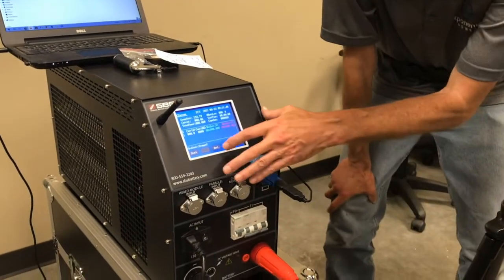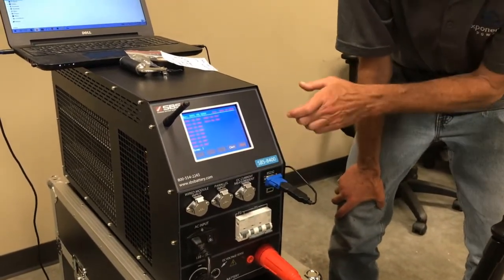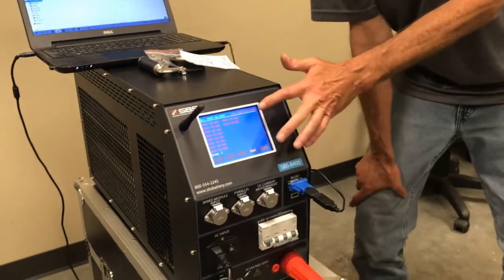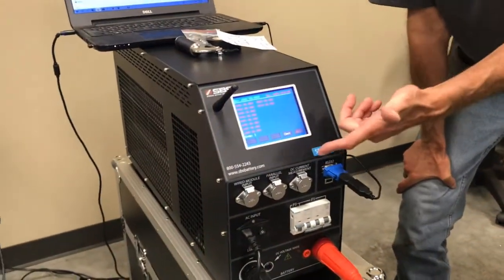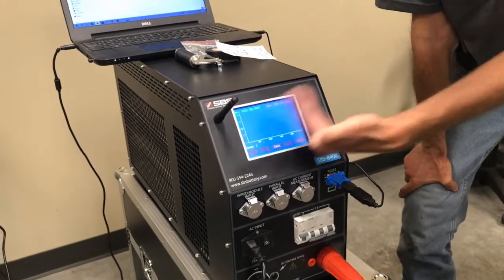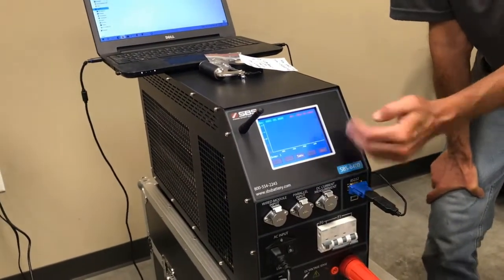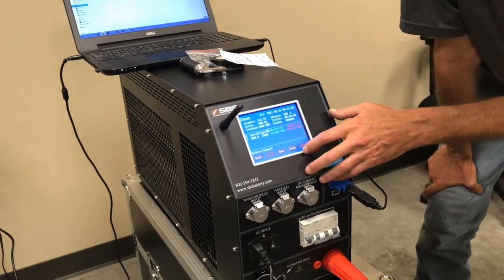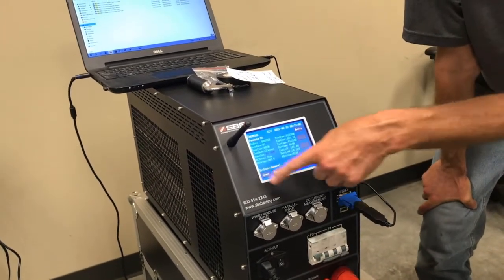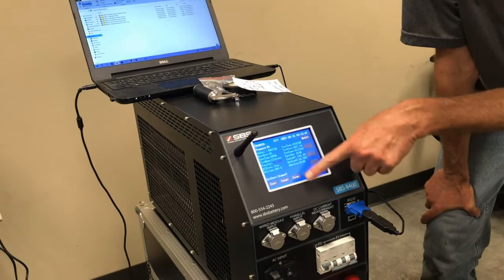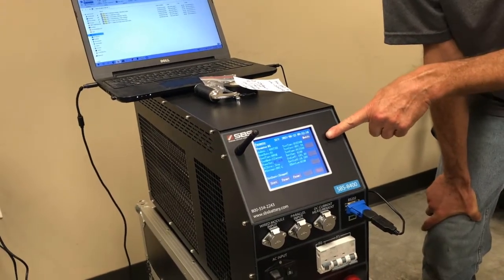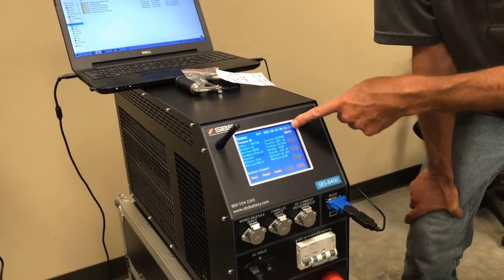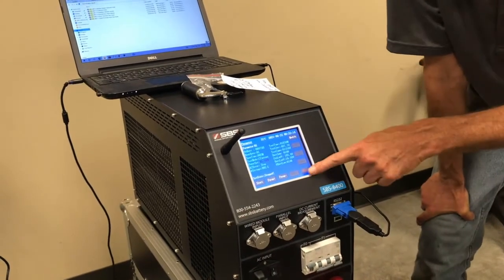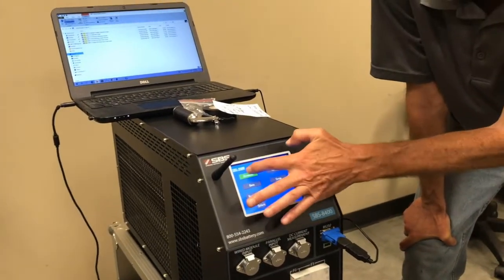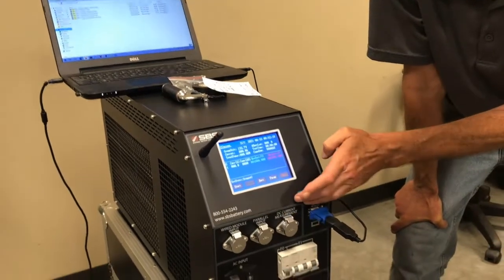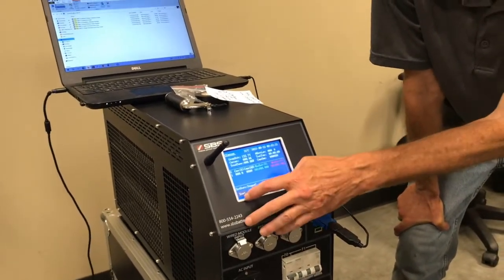If I had the individual modules, I could hit the battery key and I could see those individual voltages by pressing that battery key. I hit the chart button and they would be in a graphical format. I can go back and I can hit the parameter screen and I can review my test parameters, make sure they're set correctly. I can modify them if needed. If not, I can just exit back out, back into discharge, my summary screen.